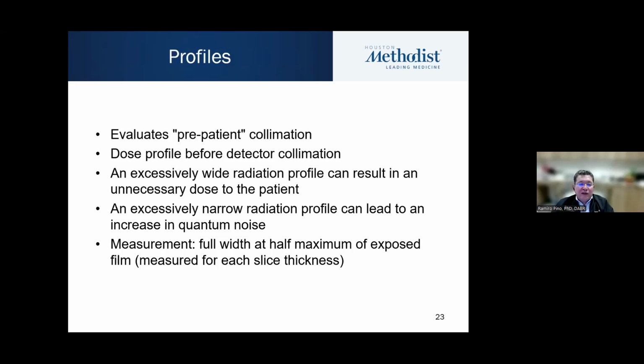We have profiles in the beam that comes out of the X-ray tube. One of the collimation systems is the pre-patient collimation system, which collimates the beam coming out of the X-ray tube before it hits the patient. This is important to keep under control within the specs of the vendor, because an excessively wide radiation profile will result in unnecessary dose to the patient without acquiring extra data. And an excessively narrow profile will lead to increased quantum noise, which is also undesirable.